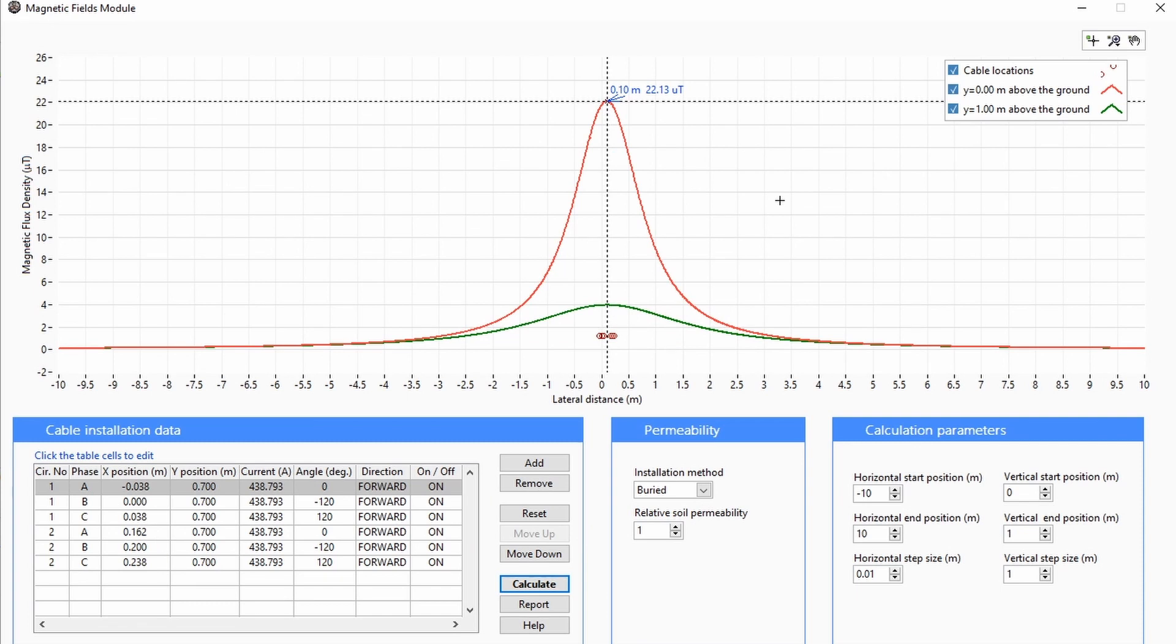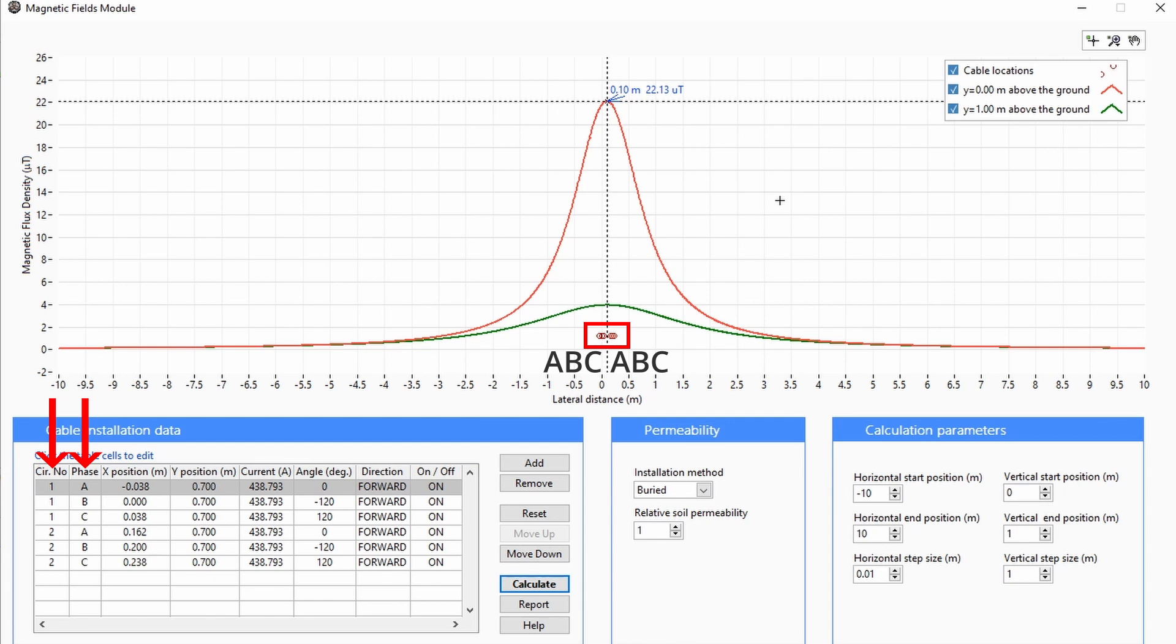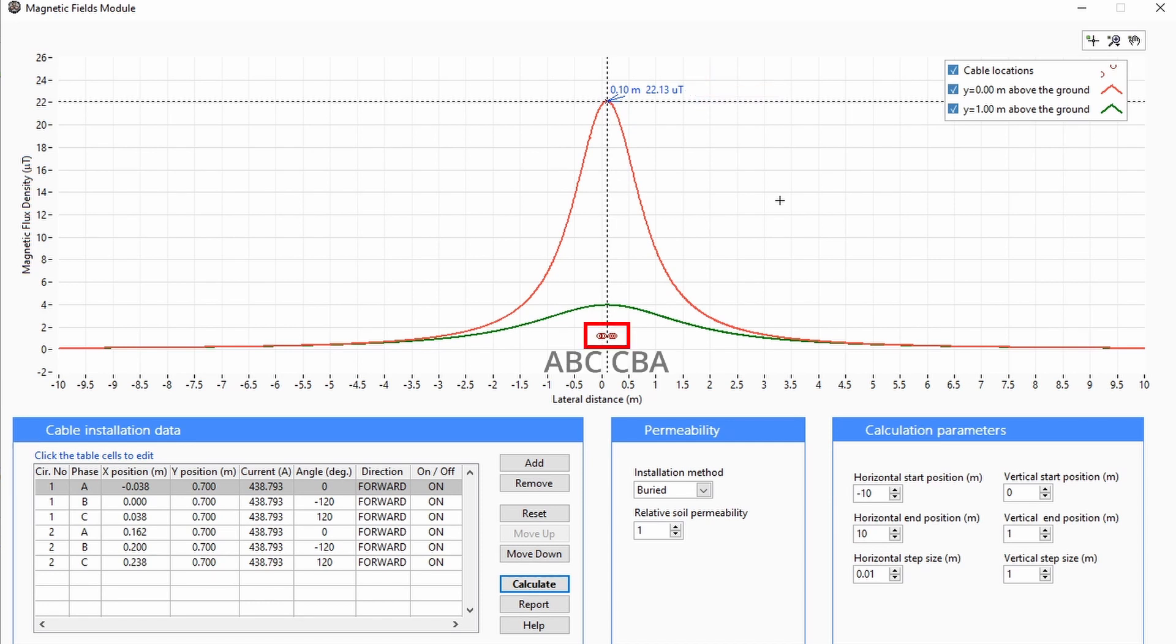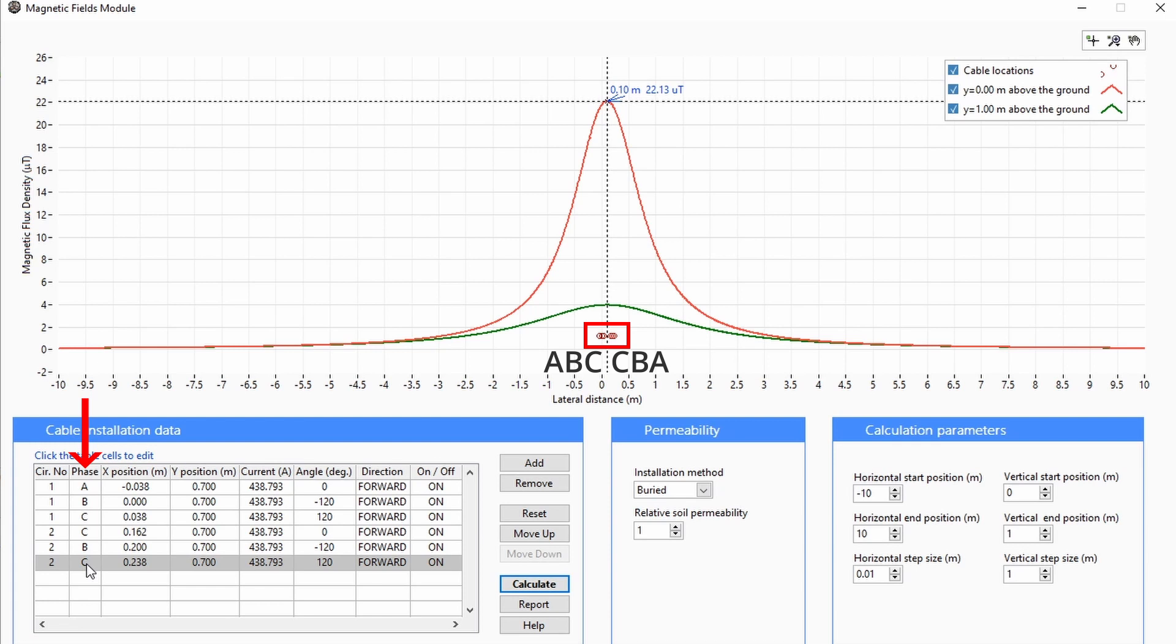Let's look at an example. The phase configuration for these two three-phase cable circuits in flat arrangement is ABC-ABC, resulting in a maximum magnetic field density of 22.13 microtesla. The optimal phase arrangement is ABC-CBA. If we update the table accordingly and recalculate, we see that the magnetic field density reduces by 70%.